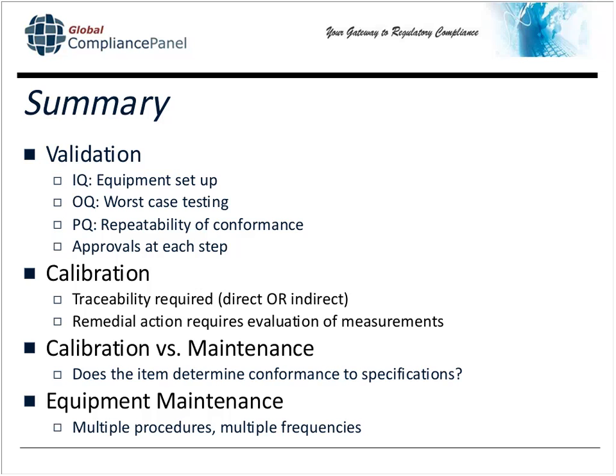And if you have remedial action, if you've got to bring something into calibration because it wasn't, you've got to evaluate the measurements that were made during the period of time during which the piece of equipment may have been out of calibration. Normally speaking, if the item determines conformance to specifications, you're going to calibrate. If it's used as an aid in manufacturing, you're going to use maintenance. As I said, there are definitely times where you maintain items that are calibrated. And equipment maintenance is a little more involved than calibration to some extent, because each piece of equipment has multiple procedures and multiple frequencies within each of those procedures.